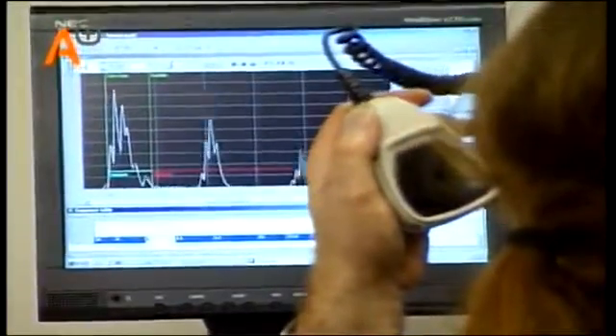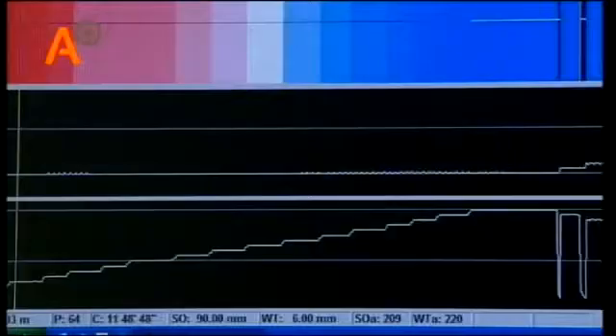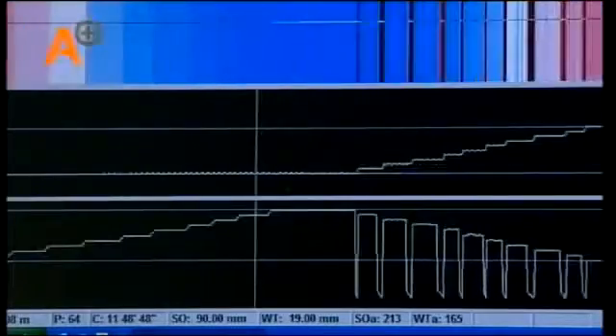In a liquid-filled tank, one sensor will be moved over this step wedge. These steps will show up on the computer screen. With this information, the ultrasonic system is calibrated.